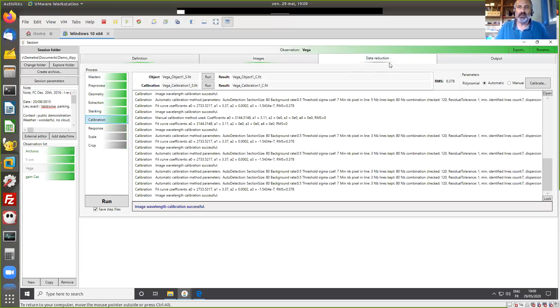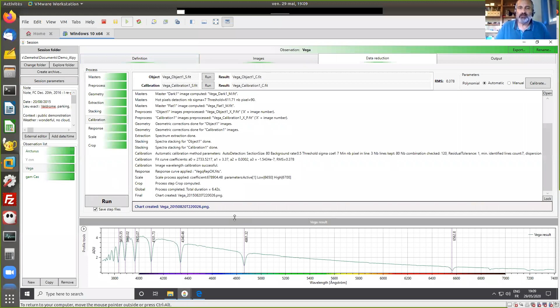Okay, so really when we talk about calibration, wavelength calibration in Demetra, this is very, very easy. Well, it's done, and you can see that the spectrum is already calibrated, and at the end of the processing, we display the Balmer lines just to have a quick view of the quality of the calibration. Okay, so this is the normal way. So this is why I told you that we could stop the meeting here. So how do we calibrate a spectrum in Demetra? That's just click on the button, and that's done.